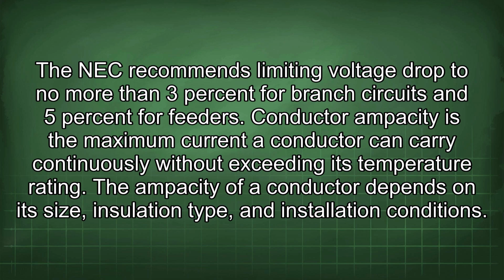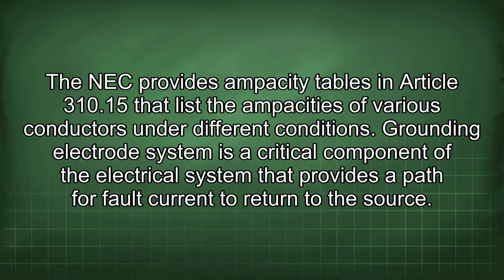Conductor ampacity is the maximum current a conductor can carry continuously without exceeding its temperature rating. The ampacity of a conductor depends on its size, insulation type, and installation conditions. The NEC provides ampacity tables in Article 310.15 that list the ampacities of various conductors under different conditions.